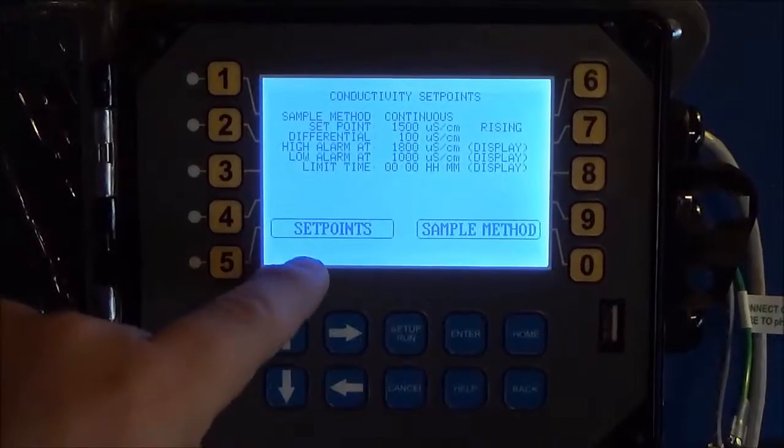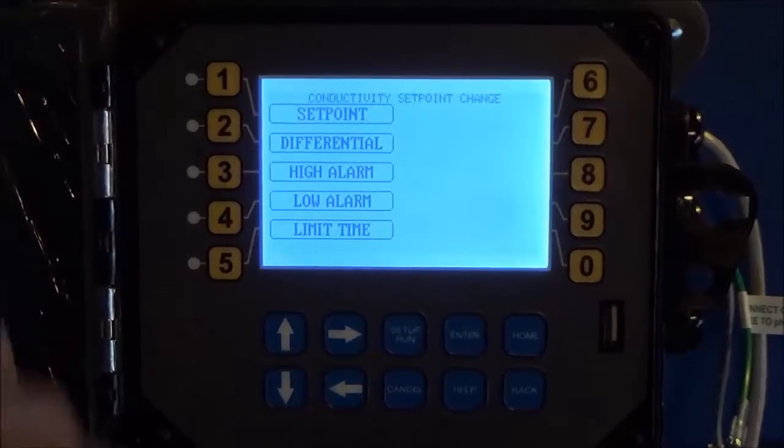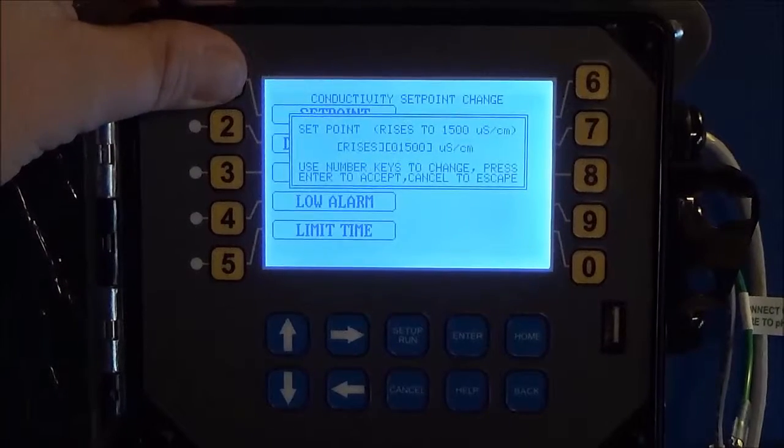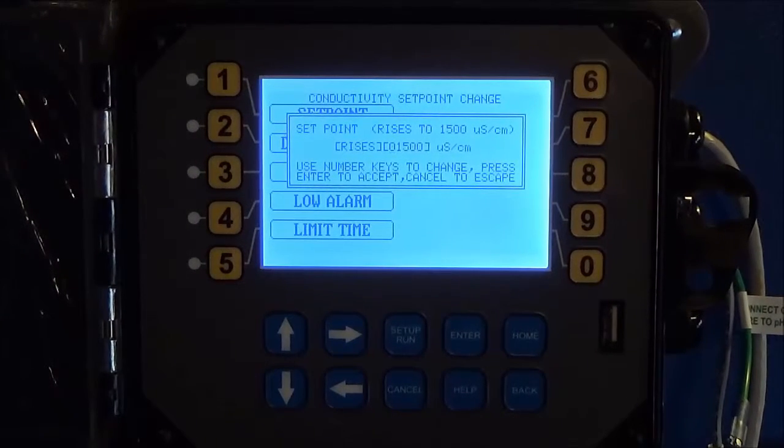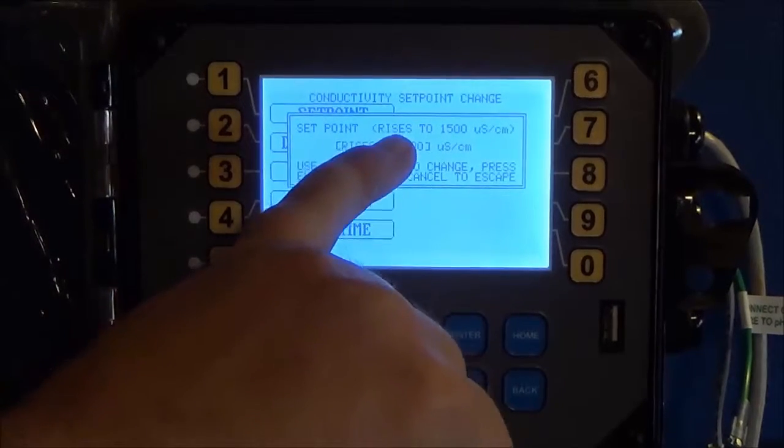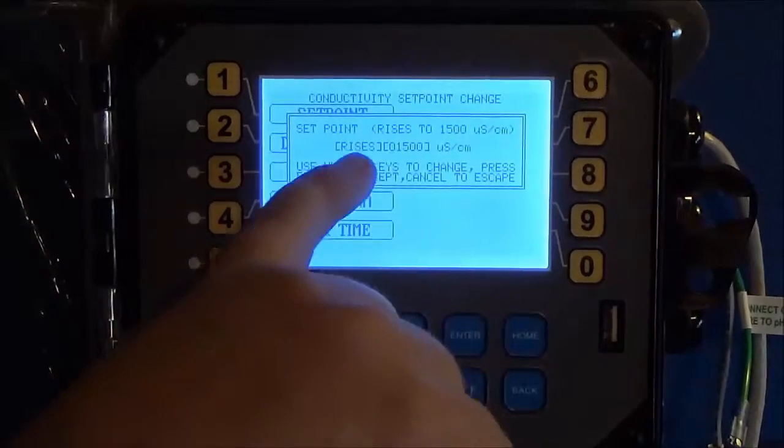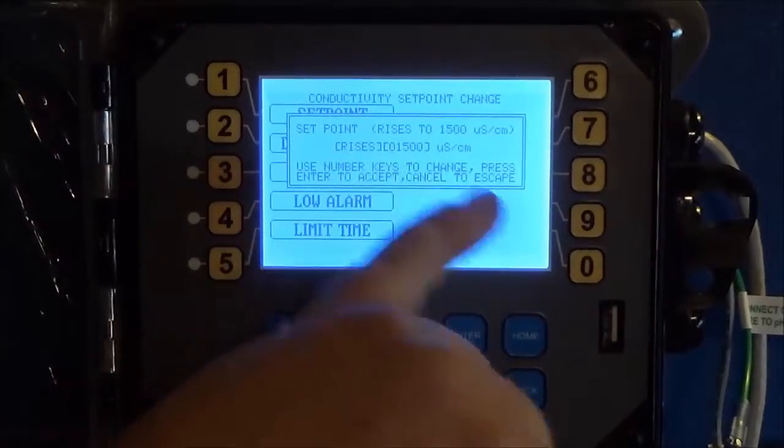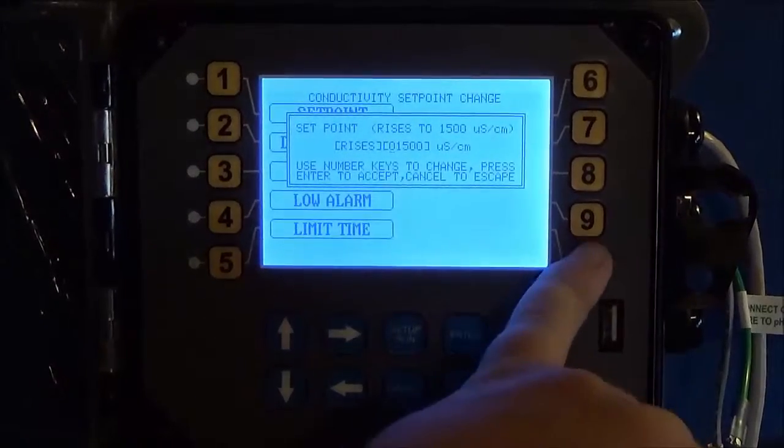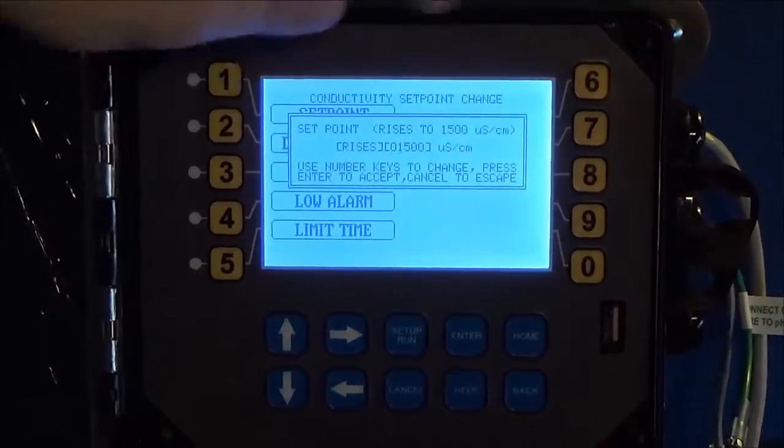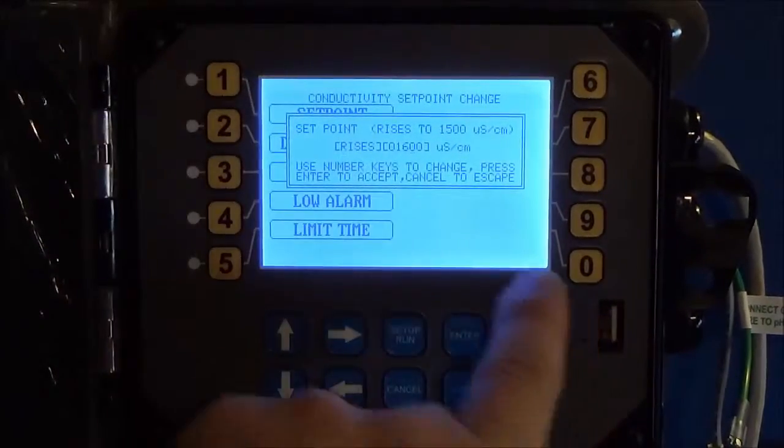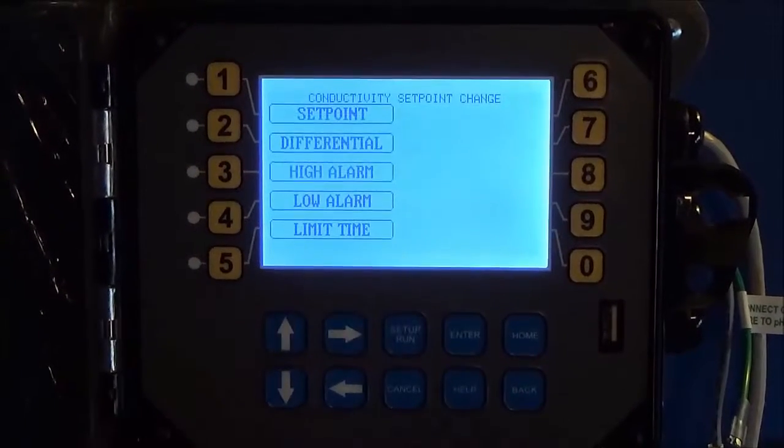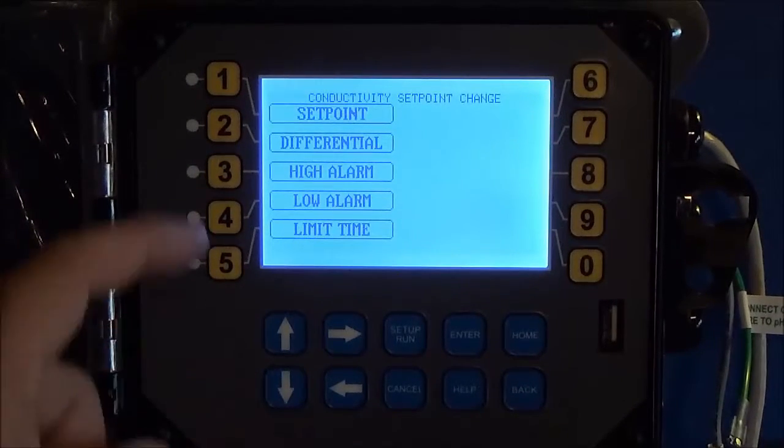So we'll go into setpoints, hit setpoint, and now we've got this pop-up screen that tells you right now it's set at a rising setpoint to 1500. If I want to change that then I can just use the number keys, zero, one, six, zero, zero. Hit enter. Now I've taken that setpoint.